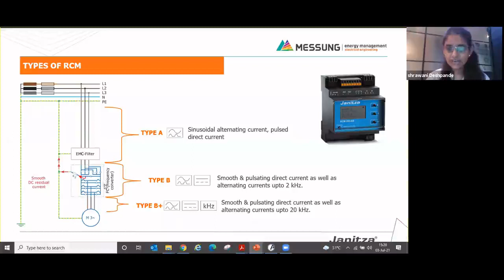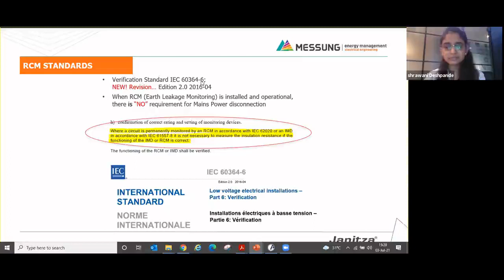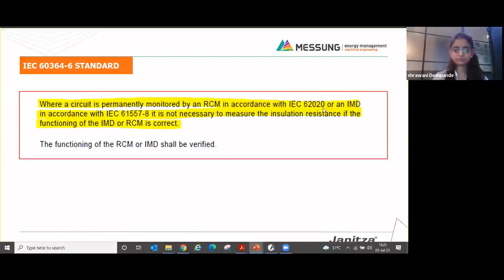Now, as far as standards are concerned, the latest standard, IEC 60364-6, also recommends RCM. It says, when a circuit is permanently monitored by an RCM in accordance with IEC 62020, or an insulation monitoring device in accordance with IEC 61557-8, it is not necessary to measure the insulation resistance if the functioning of the insulation measurement device or residual current monitoring is correct. And as I said, Janitza has products which comply with IEC 62020.